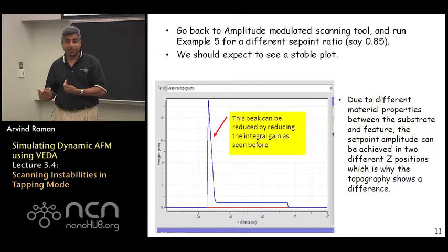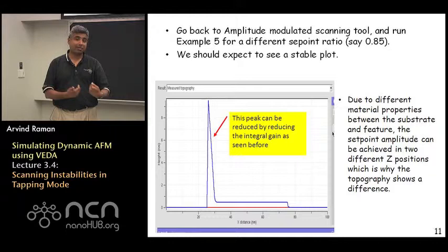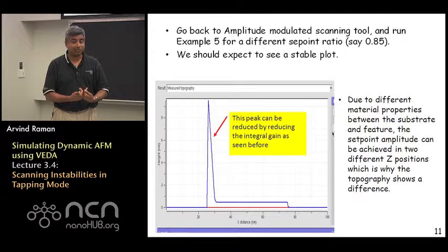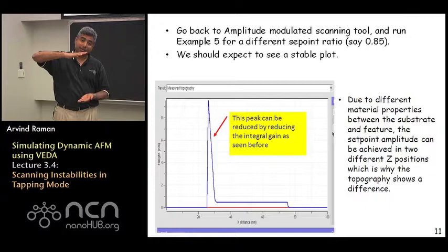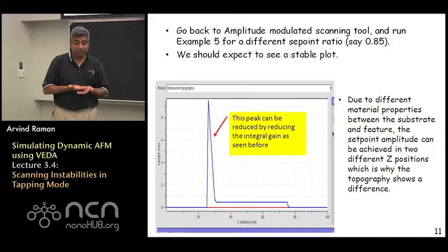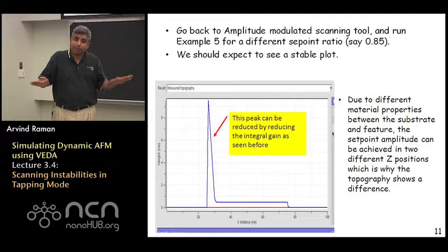And the answer has to do with the fact that at 85 percent set point we are able to maintain a constant amplitude as we go over from the substrate to the feature. However, 85 percent set point on the substrate corresponds to a repulsive regime oscillation. 85 percent set point on the adhesive feature corresponds to an attractive regime of oscillation. In the attractive regime of oscillation, the Z position of the cantilever tends to be a little further away from the sample and the tip doesn't come as close and doesn't indent as much into the sample. As a result, the feature is going to appear to be slightly elevated compared to on the substrate.